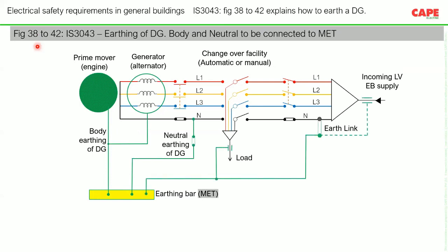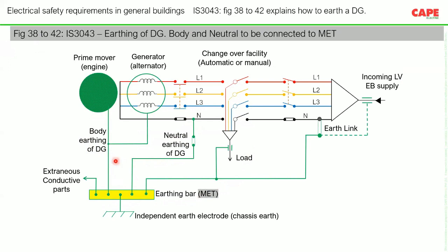This picture from IS 3043 again is just to show that earthing doesn't mean neutral two separate pits, bodies two separate pits for DG and transformer. It is absolutely wrong. What you should do is a protective equipotential bonding. Neutral of the transformer or DG has to be connected to an earthing bar. This picture is basically for a place where you have your own DG, body, alternator, and neutral connected to the common bus bar. And this is the correct way.